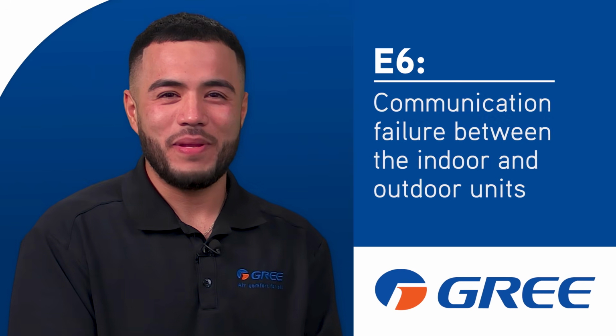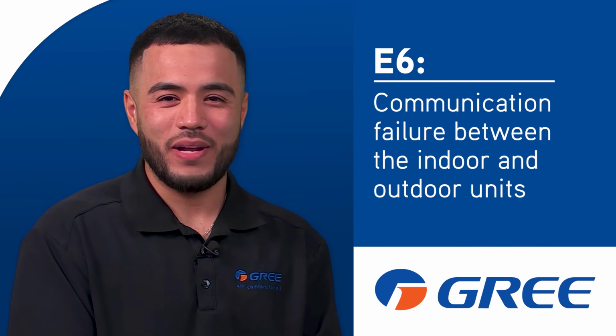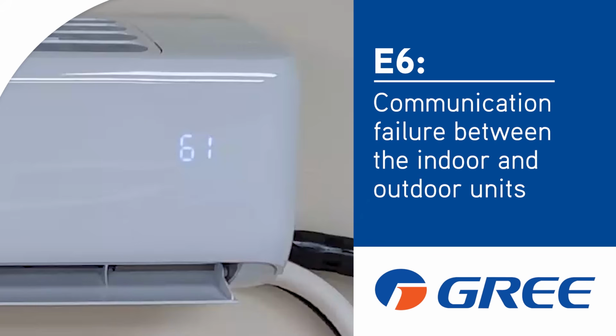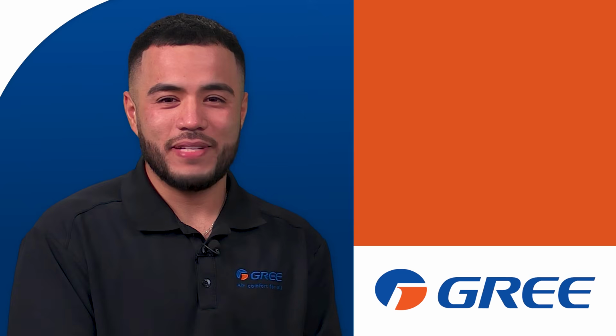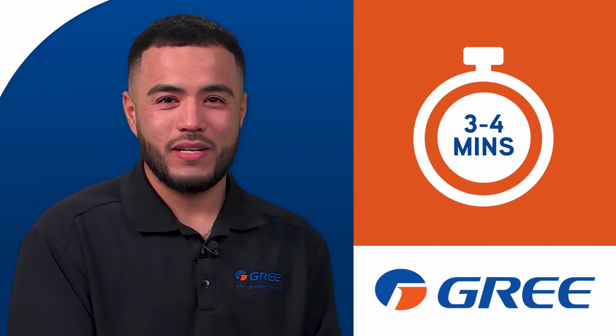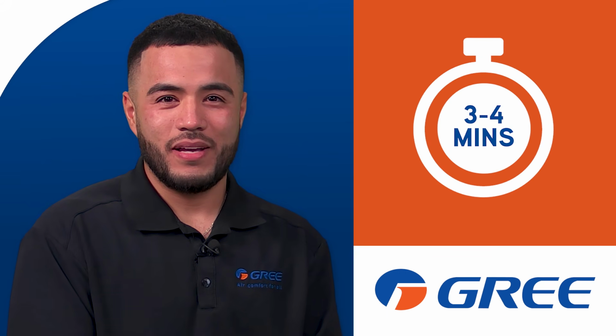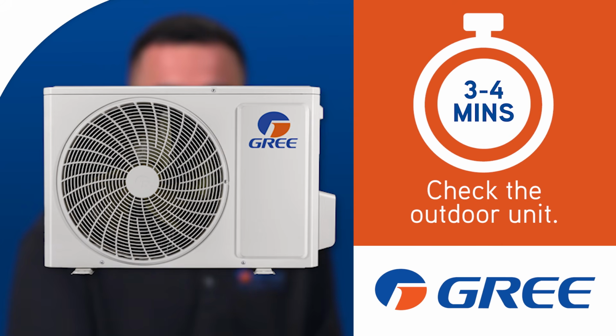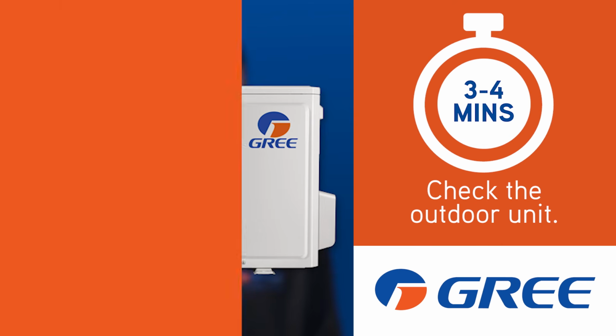E6 means that there's a communication error between the indoor and the outdoor unit. If it shows up right at startup, the issue is likely in the indoor unit. If it takes a while, say 3 to 4 minutes after the system has been powered on, it is likely at the outdoor unit. Let's walk through the troubleshooting steps.